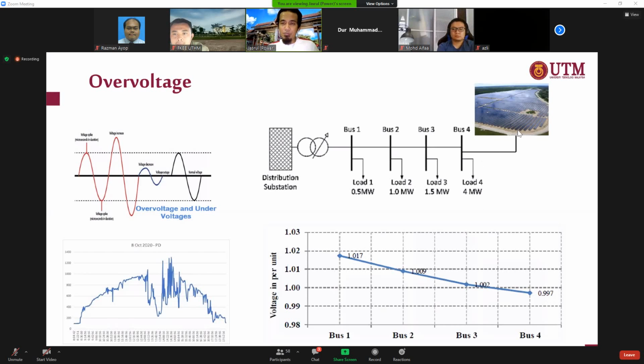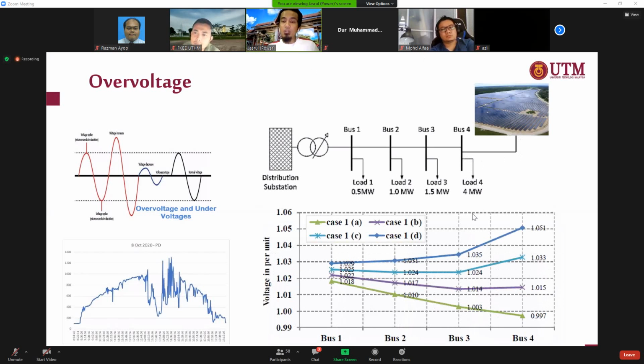And what happens if suddenly we inject PV at the end of the bus? Okay, because it's a distribution system, isn't it? So this is the voltage pattern that we have. I put it in 4 cases: case A, case B, case C, case D. The higher the PV size, or the higher the energy injected by the PV, the voltage at the end of the terminal will increase. So you can see that here is 0.997, and after that it might increase until 1.05, which is 5% above the normal standard value. Okay, but it's still within the limit. But you can imagine if you have a larger power, so a larger energy to be injected, you might have a larger voltage at the terminal. So you might face an over voltage problem.